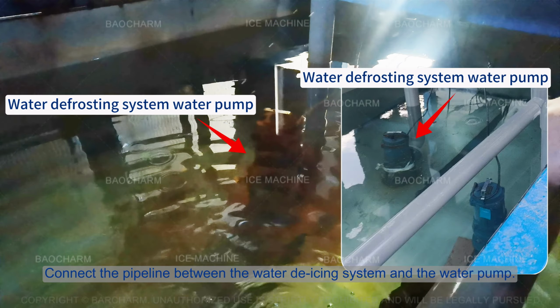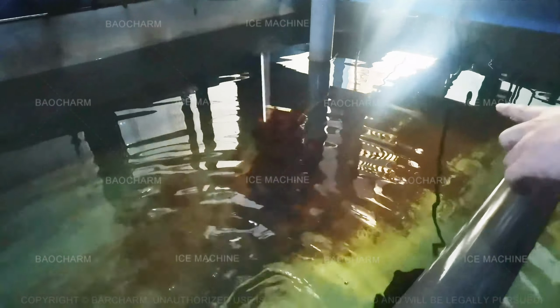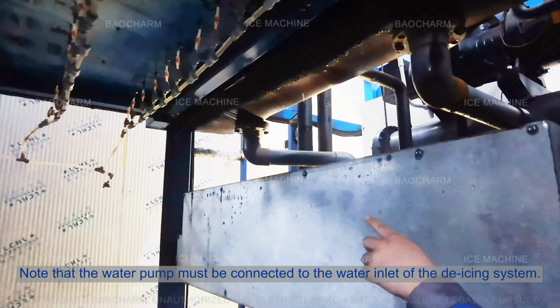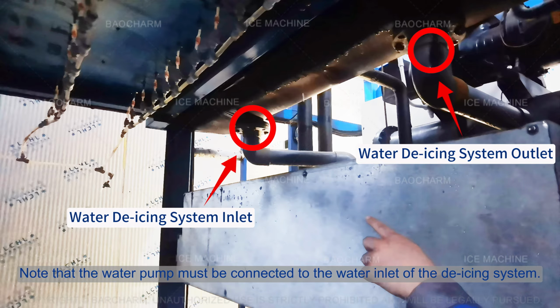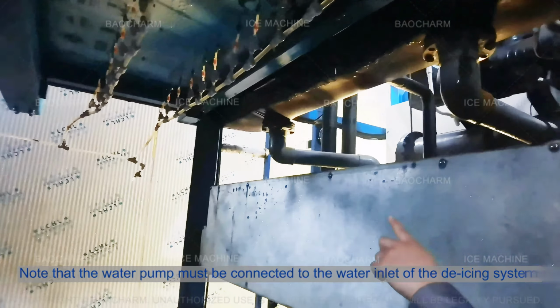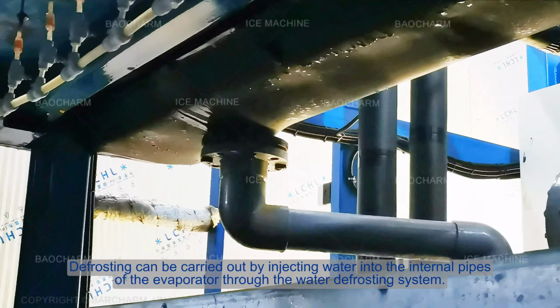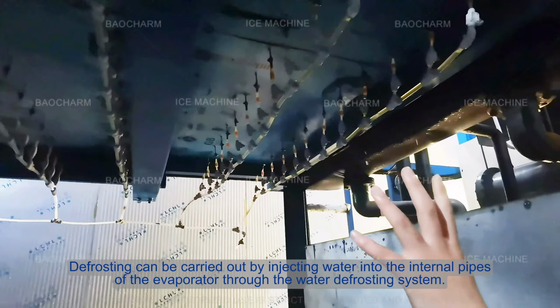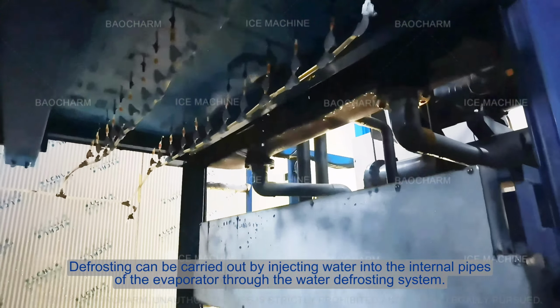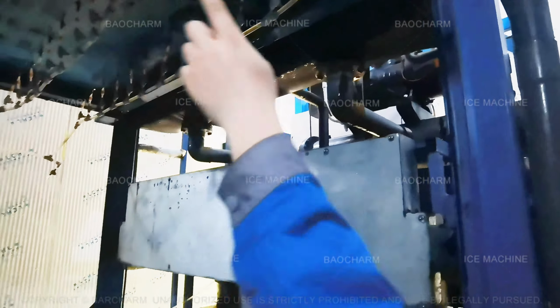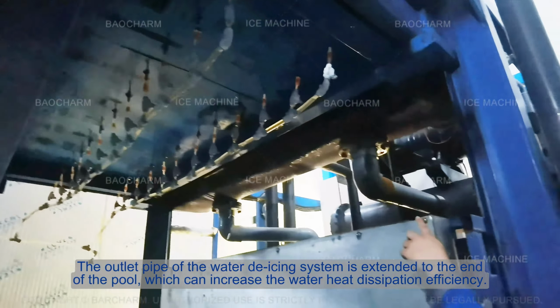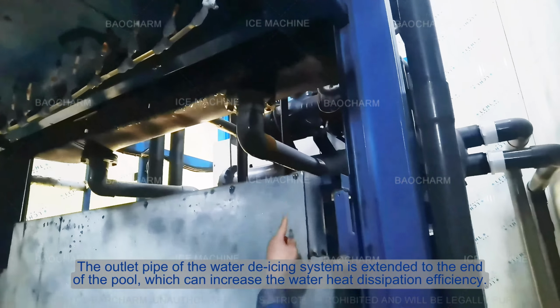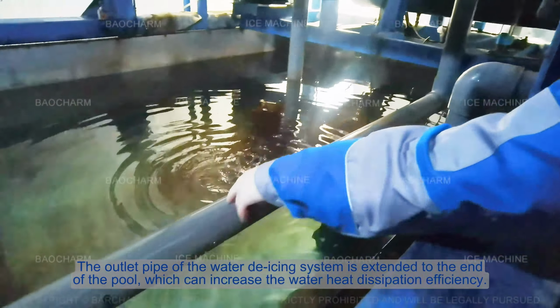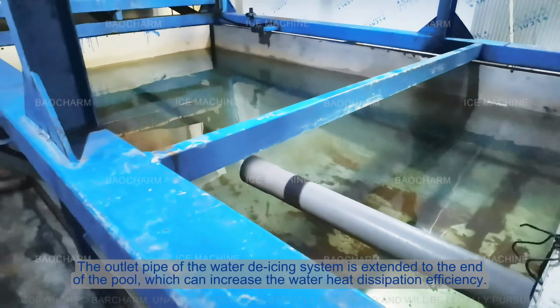Connect the pipeline between the water de-icing system and the water pump. Note that the water pump must be connected to the water inlet of the de-icing system. Defrosting can be carried out by injecting water into the internal pipes of the evaporator through the water defrosting system. The outlet pipe of the water de-icing system is extended to the end of the pool, which can increase the water heat dissipation efficiency.